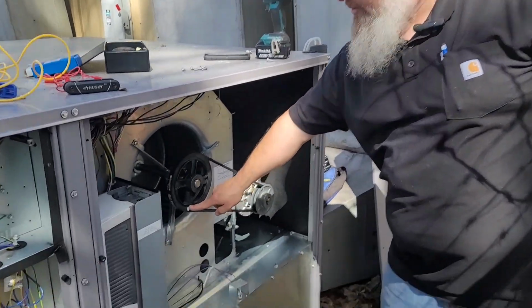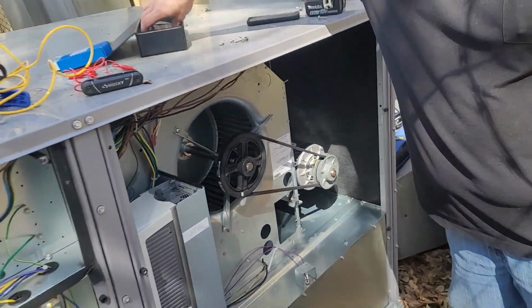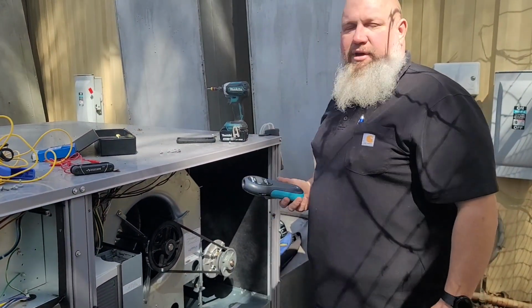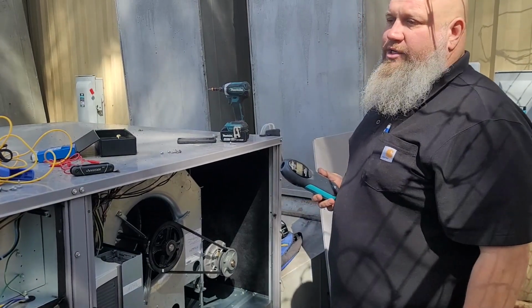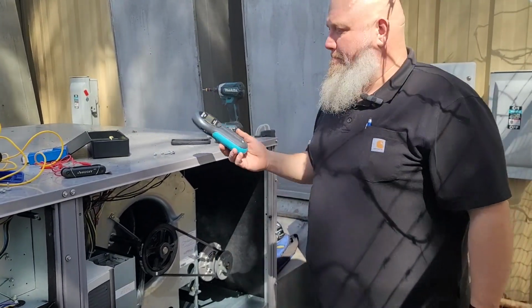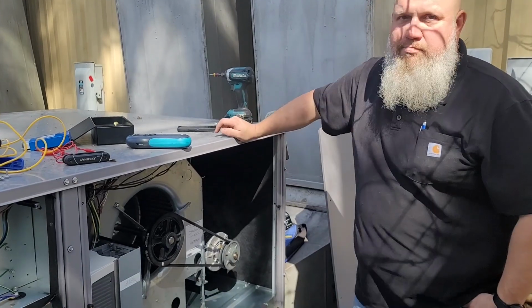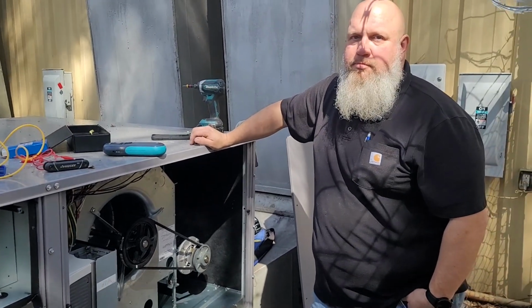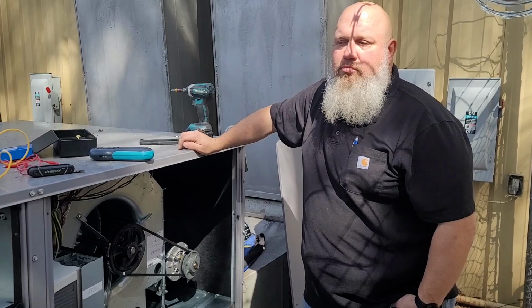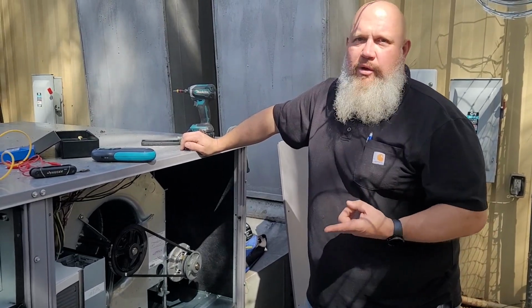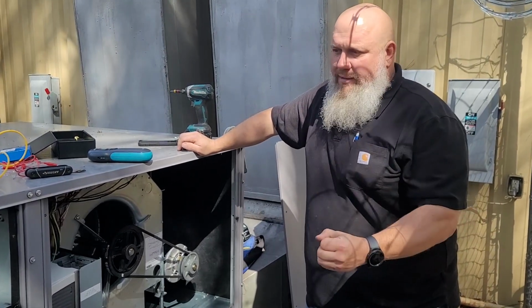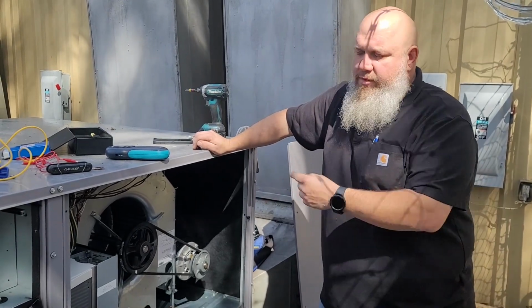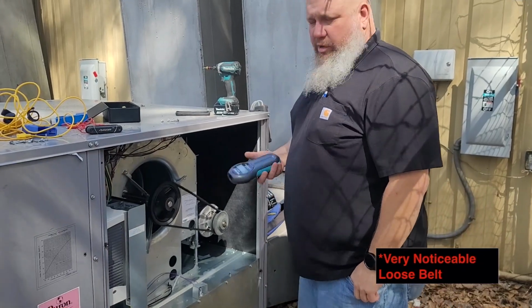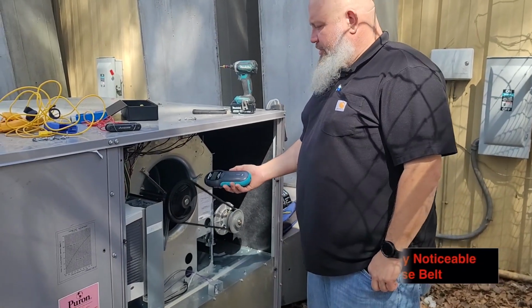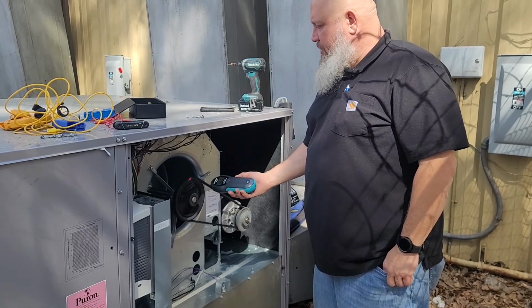So I've put reflective tape on here so we can use our optical tachometer to see how fast the blower wheel is going, and we're going to check that with the chart and see where we're at. Mike, I noticed there's a VFD on the unit. So what do you have to do to make sure that the motor's at 100% so you can check the proper RPM? You've got to jump out, make sure Y1 and Y2 are both jumped, and sending signal to the VFD to go to full speed. Tell us what you're doing right now. We're going to use the tachometer to check the RPM with the little piece of tape we put on.